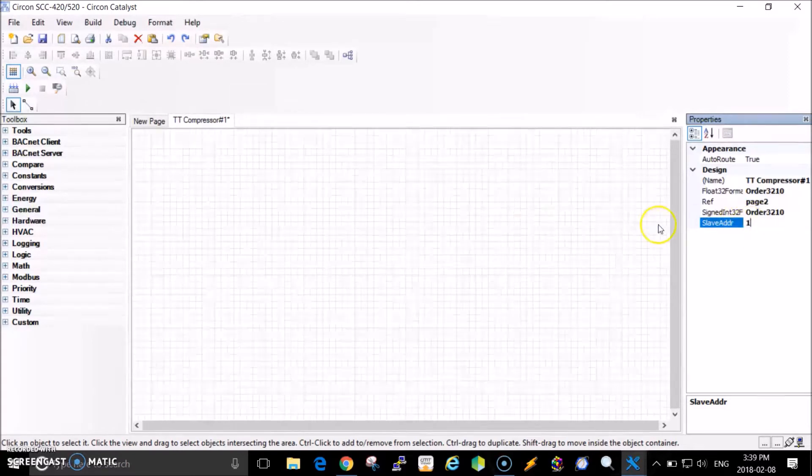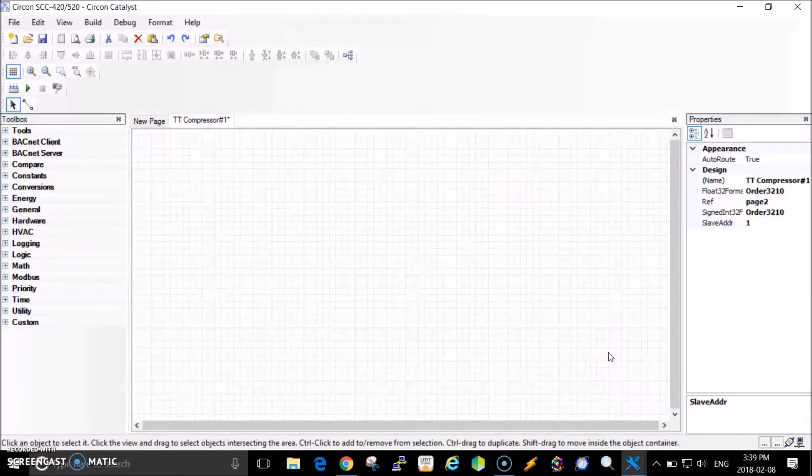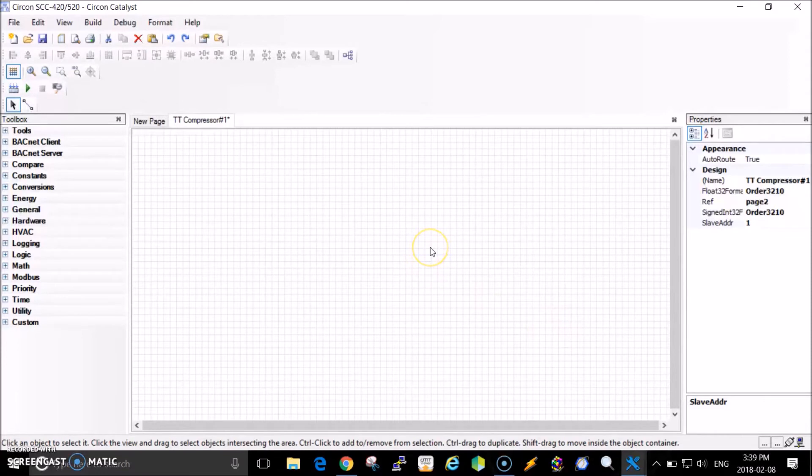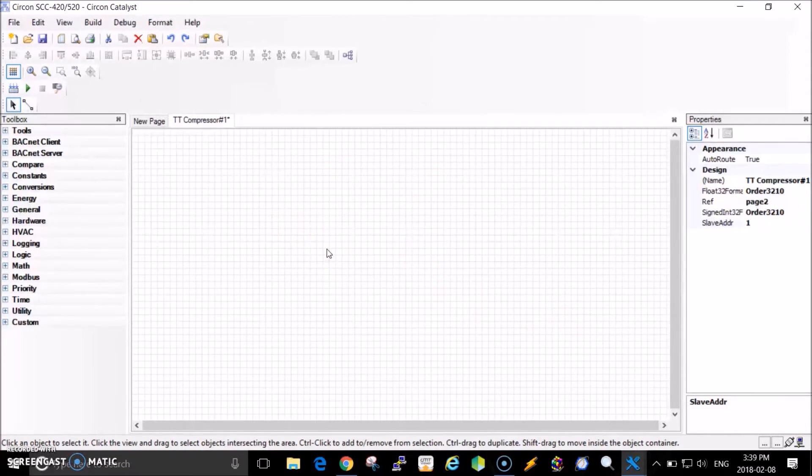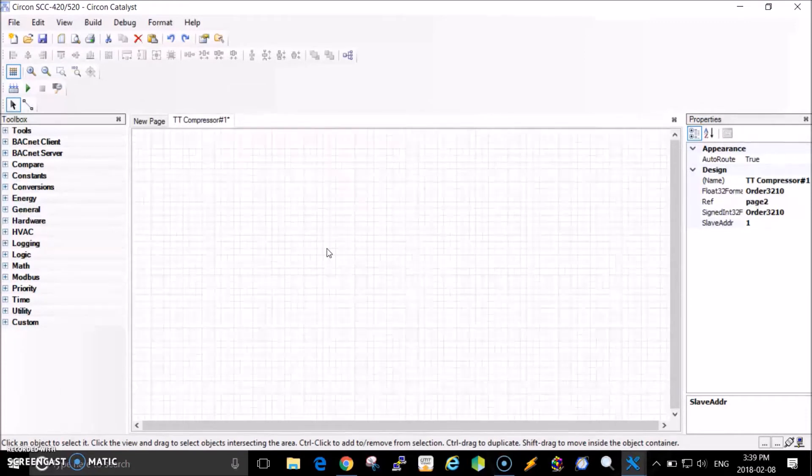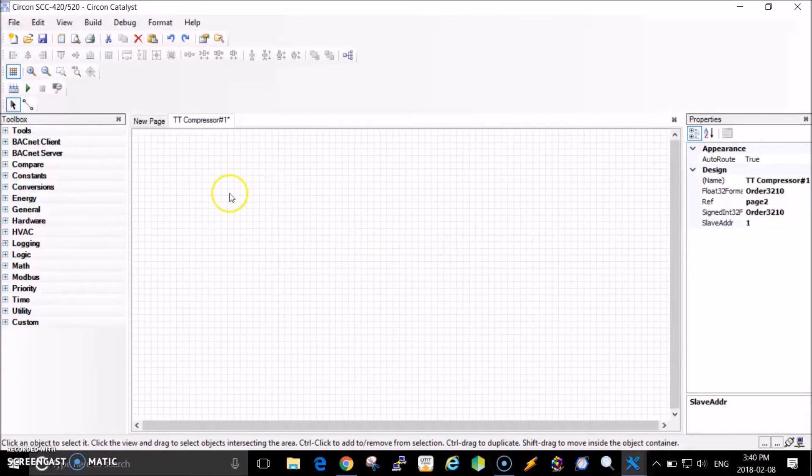Now I can drop some Modbus blocks and start communicating with the device. One thing to remember is that Catalyst uses a Modbus addressing format called addressing base zero. From what I've read, the Danfoss compressor uses Modbus addressing base one, so whatever the register number is, you have to subtract one when you put it into the Catalyst project.